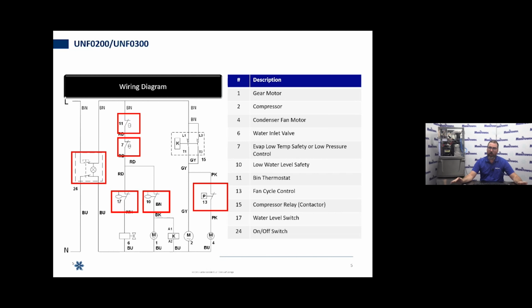Now, if we find that all of the safeties are in fact closed and that we have continuity through them and we still have a compressor that doesn't want to start up, then we're going to start wanting to test that compressor itself. Maybe we have a shorted motor in the compressor, start components, something of that variety. But the first step and the most crucial step is to make sure that we follow that flow of electricity through all those safeties. One open safety is going to stop this machine dead in its tracks.